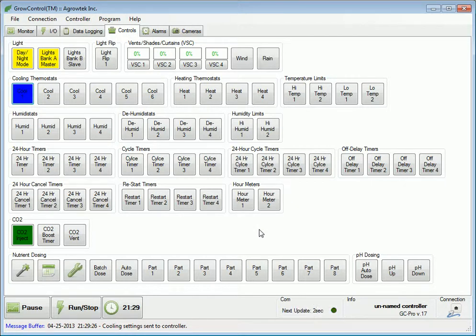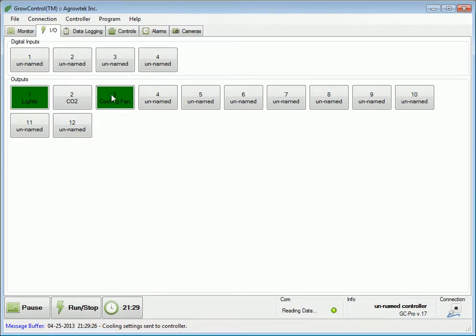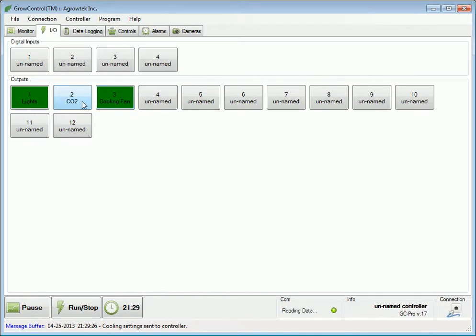We can see that the cooling thermostat has been activated. When we travel to the I/O tab, we can see that the cooling fan is indeed on, and the interrupt that we've specified has turned the CO2 output off.